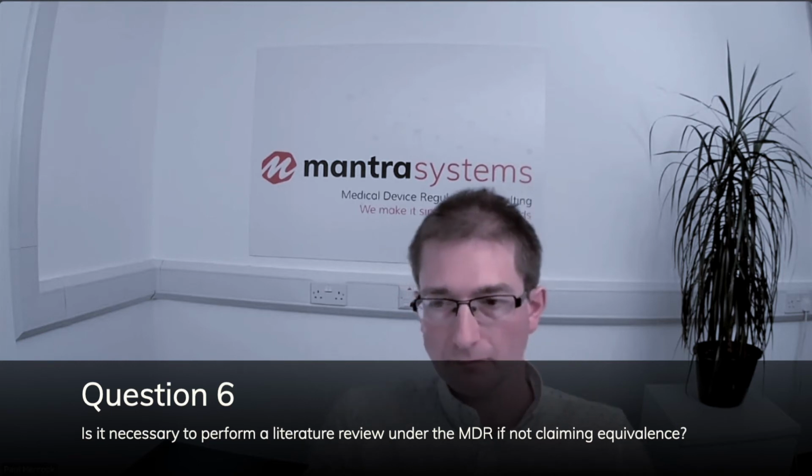Another question. Is it necessary to perform a literature review under MDR if you are not claiming equivalence? Yes. So a literature review is absolutely essential under the MDR. It's one of the bits that's really attained prime importance, whether you're claiming equivalence or not.